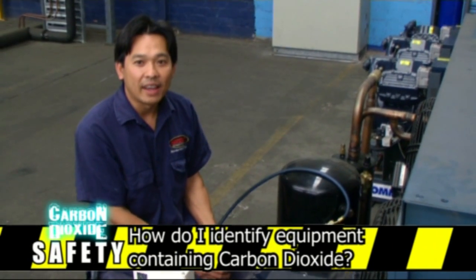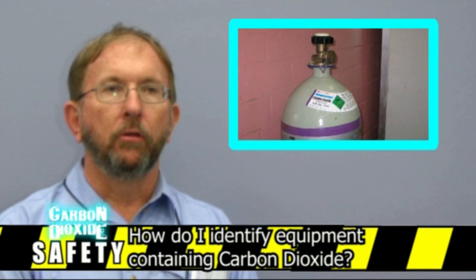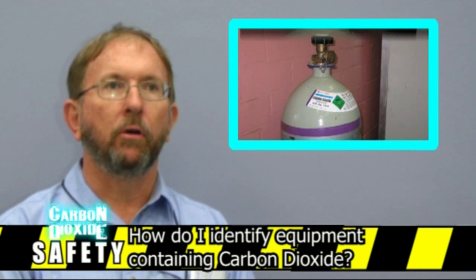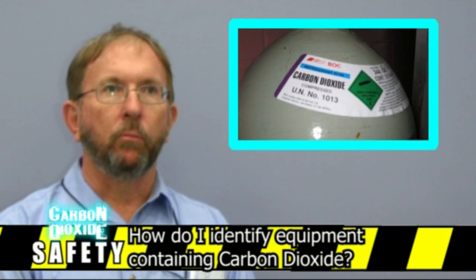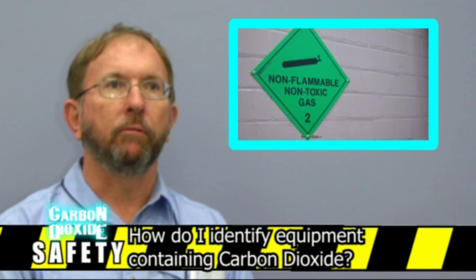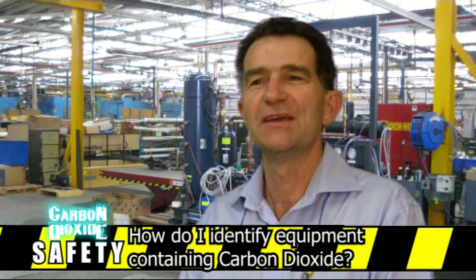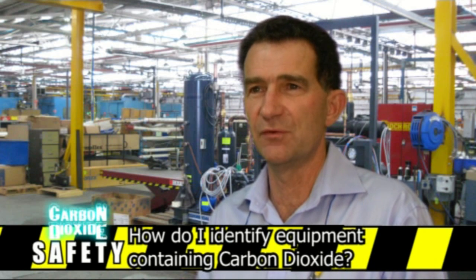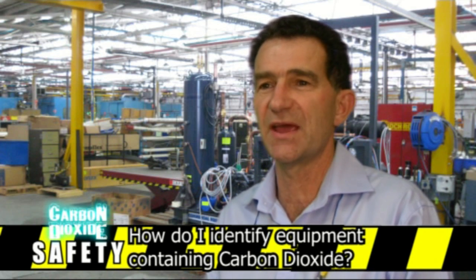How could I identify equipment containing CO2? Carbon dioxide is also known as refrigerant R744. Ideally, I would look for identification on the system with some labelling. If there is no labelling on the equipment whatsoever, I would treat the system as though it contained a hydrocarbon refrigerant that is highly flammable. The equipment should be labelled saying carbon dioxide, CO2, or the refrigerant number R744. If it's not labelled, you should exercise a lot of caution in establishing what the actual gas is.